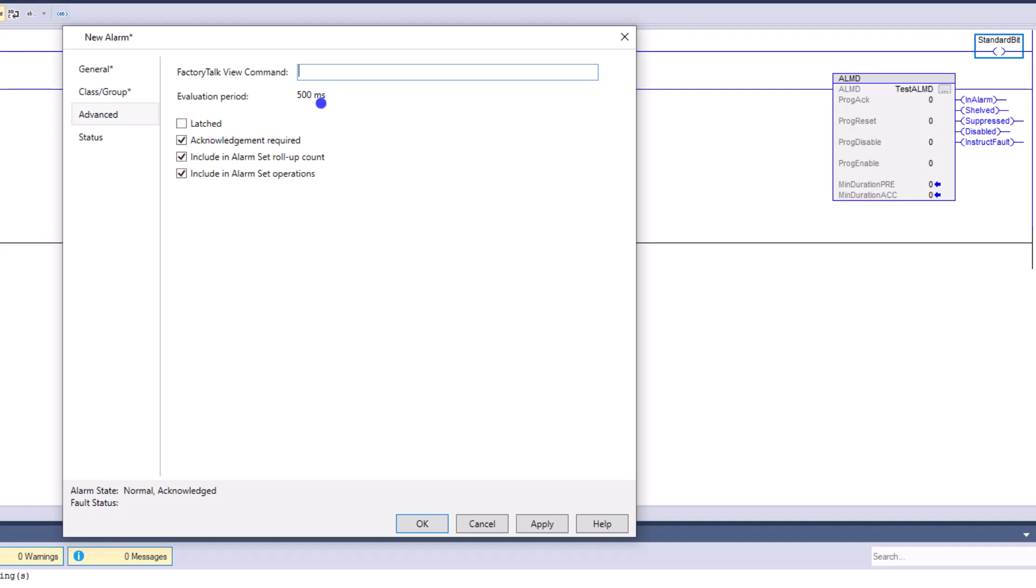That is subject to change in future versions, because that is a limitation that I feel, if you're trying to, in most applications, you're going to, or most machinery that you program or you're working on, you want to have, when your alarm happens, you want to have exactly when it happened. So you have a timestamp of when it happened. The ALMD on the counter side to that does have that ability. So there is no 500 milliseconds delay on that ALMD. Although with this feature there is.